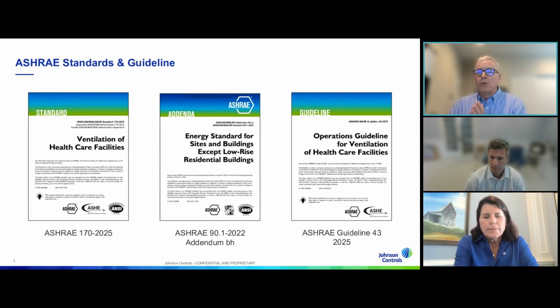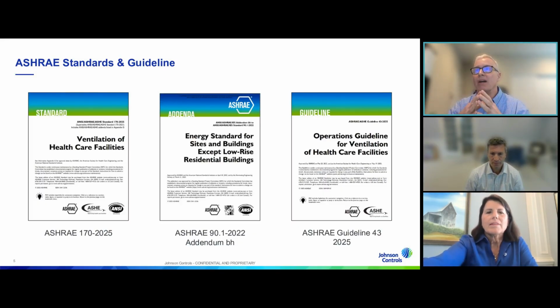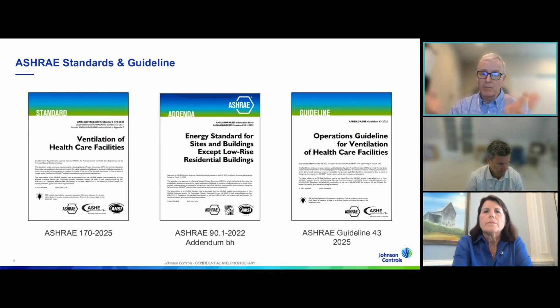So when we talk about the performance itself, what those areas are, what we need, the parameters basically that we have to have these spaces operating within, we're talking about ASHRAE 170. That's talking about the ventilation within these spaces, what the relative humidity is, how many air changes we need, what kind of pressure relationship we need to have within those different spaces. So that's really our go-to when we're looking in that space.